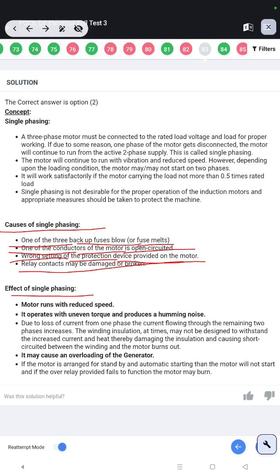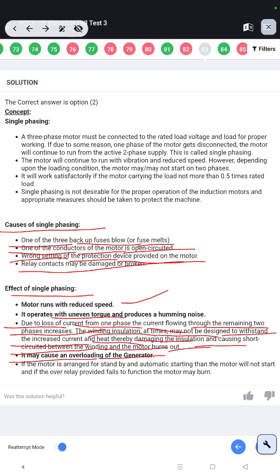Effect of single phasing: the motor runs with reduced speed. Second, it operates with uneven torque and produces a humming noise. Third, due to loss of current from one phase, the current flowing through the remaining two phases increases. The winding insulation at times may not be designed to withstand the increased current and heat, thereby damaging the insulation and causing short circuit between the winding and the motor burnout. It may cause an overloading of the generator. If the motor is arranged for standby and automatic starting, then the motor will not start, and if the overload relay provided fails to function, the motor may burn.